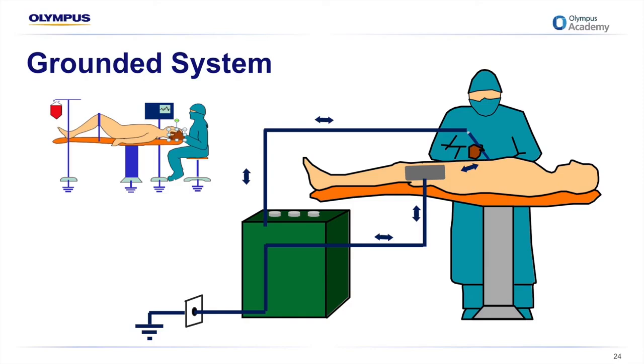In such cases, if return electrode contact or conductivity is compromised, or if resistance at the active electrode site increases significantly, such as during eschar buildup, the current has a difficult time returning to the return electrode and may thus seek the path of least resistance and exit the patient at an alternate site. The current may exit the body at a site that has a small surface area, such as the tip of a finger touching a metal surface or an ECG lead, and the patient is burned. Consequently, always use grounded generators with extreme caution.